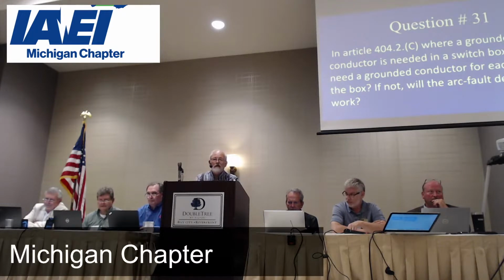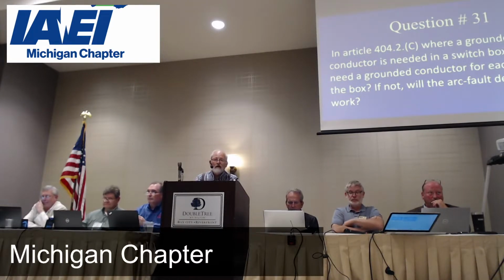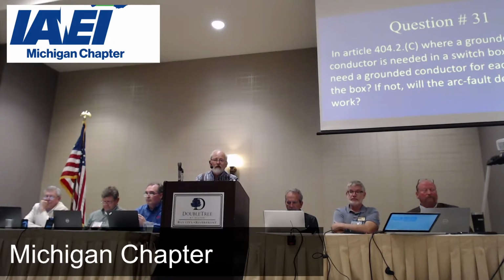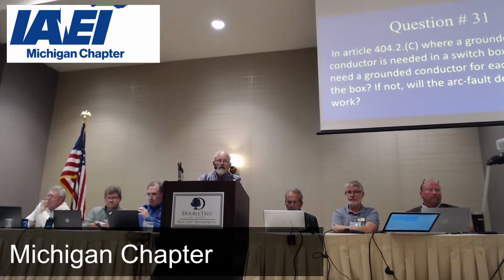Tom, if I understood you right, you said if a light is controlled from another location, the other location doesn't require the neutral. Right, so let me read it verbatim here from my NFPA link. It states in the 2017 code, where multiple switch locations control the same lighting load such that the entire floor area or room or space is visible from the single or combined switch location, the grounded circuit conductor shall only be required in one location. I ran into a situation recently.